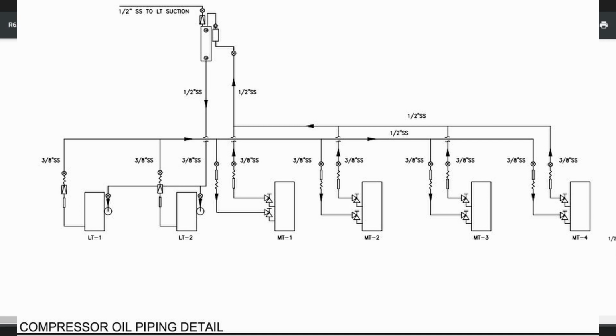On this job, we had to switch from copper cap tubes to quarter-inch stainless tubing. And fortunately, they make quarter-inch stainless tubing in any bore you want. You can get 25 thousandths or 55 thousandths. You just order the quarter-inch tubing with the right bore, and then you use compression fittings, and it works very well. Gotcha. Now, there's two things I want to bring up.